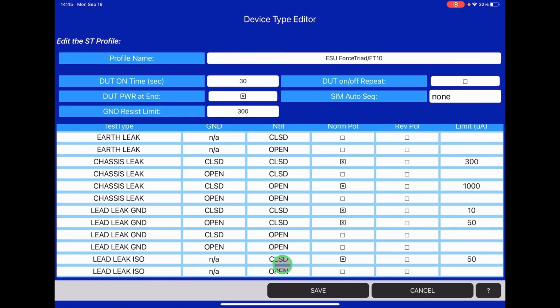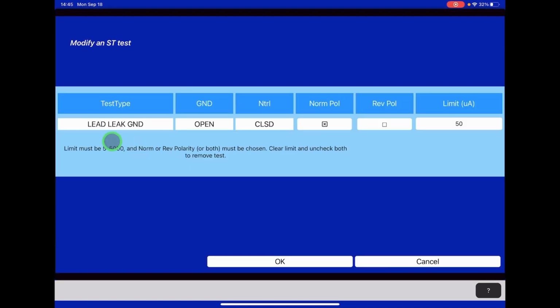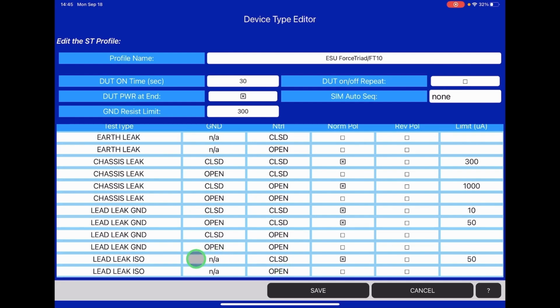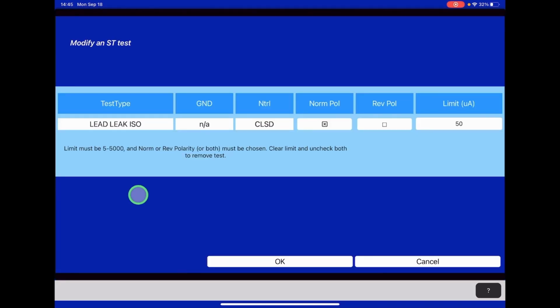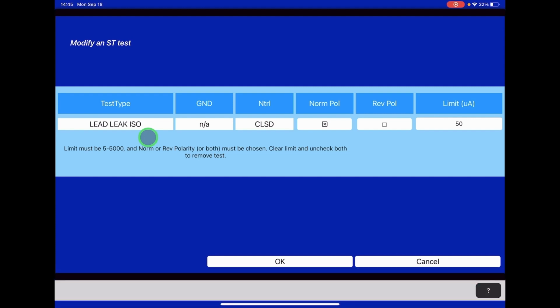which we've done here. And then the next one is a second leads to grounds test, or a lead leakage source test with the ground open, neutral closed, and the limit for this test is 50 microamps. Then the very last test is the lead leakage ISO, or lead leakage main and applied parts test, where we're taking 120 volts AC and applying it to all of the leads or applied parts, or in this case all of the outputs. Just know it is current limited.